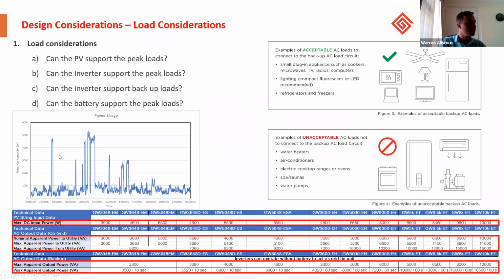Then the next thing we need to understand is, on the essential circuits, is it required that these appliances run? And if so, can the inverter support these peak loads? So if we look again at these peak loads, we have over 5 kilowatts. If we had to use the EM series, unfortunately, that cannot support the load, and we'd have to look at alternative products. In this case, the GoodWe 6000 EH would be able to deliver this 6 kilowatts to the load. So in splitting the load correctly, you may be able to supply an inverter like an EM inverter, which can supply the base load, which is less than 2 kilowatts, and supply the PV when the grid is connected with 5 kilowatts.